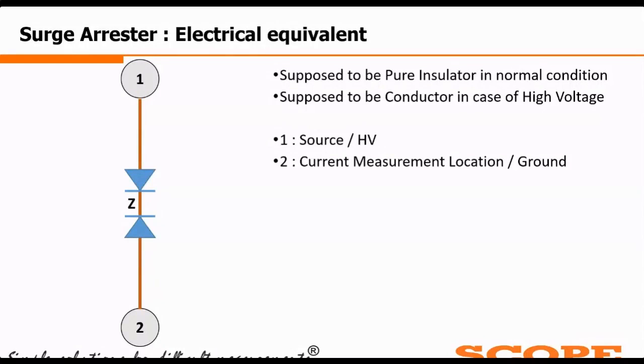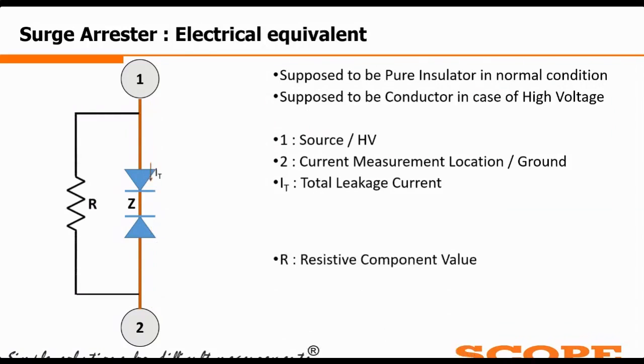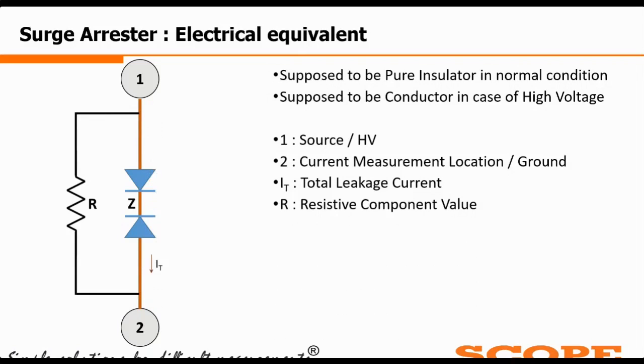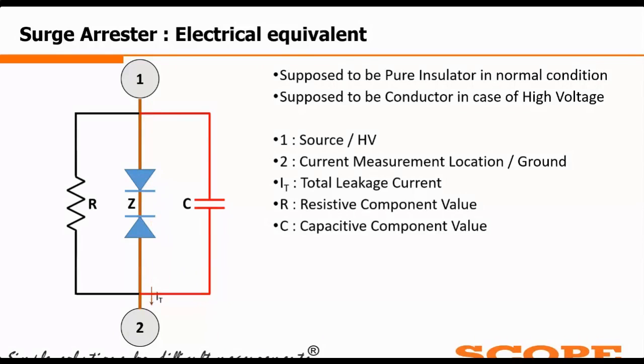Before going there, we have the current measurement, the surge counter along with the surge current meter, or LA current meter, the leakage current meter. Now if we consider the current flow, the leakage current should flow from point 1 to point 2 due to the condition of the LA, because the LA is not a pure thing. If we consider an equivalent circuit, we can consider the LA as a resistance and a capacitance in parallel. In the capacitive part there will be the capacitive current, and in the resistive part there will be the resistive current flowing. In totality, IT will be the vector summation of IR and IC.